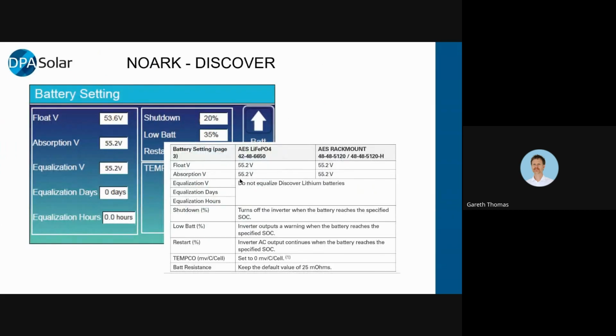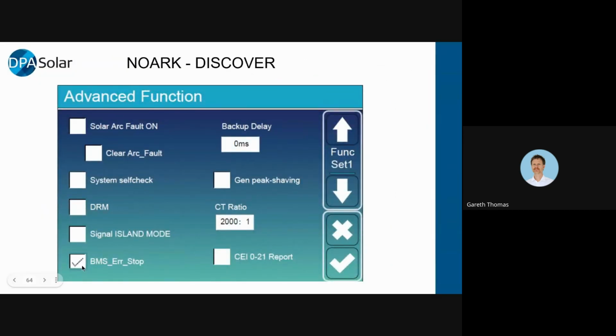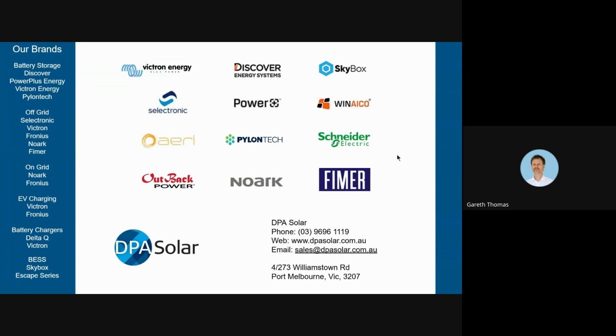And then we've set the unmanaged voltage settings in here as well. But you don't normally need to do that because I don't think it falls back to them. This is an example if you were going to do it as unmanaged. Then we've got BMS Err Stop on. We've got DRM off because we don't need it in the area that we're in. Yeah, and that's the basic setup for a Discover battery.